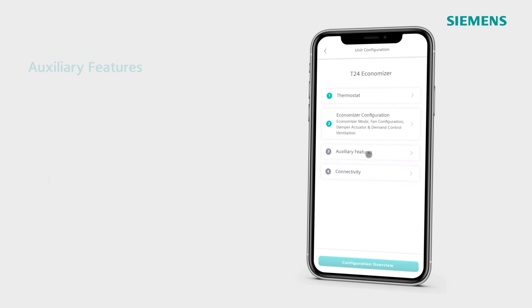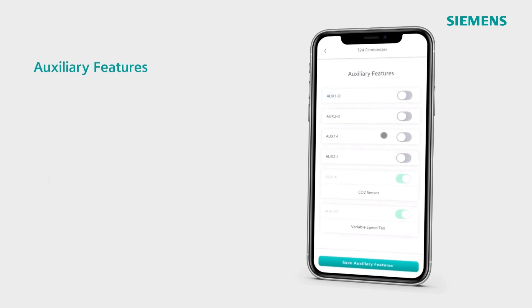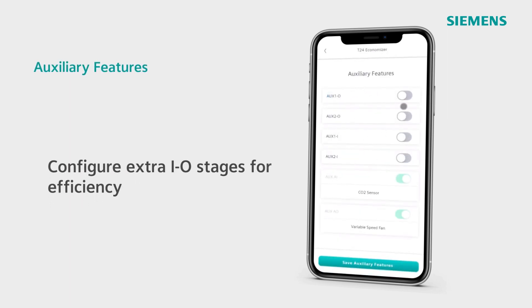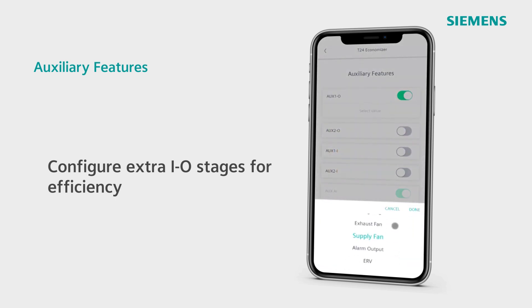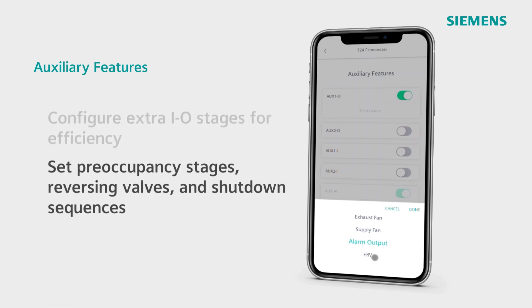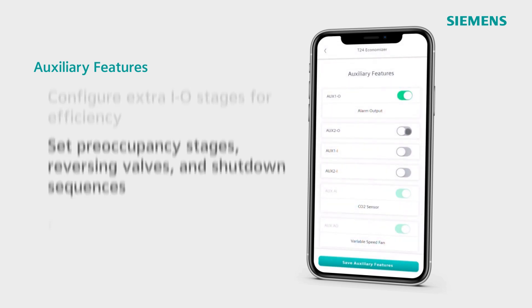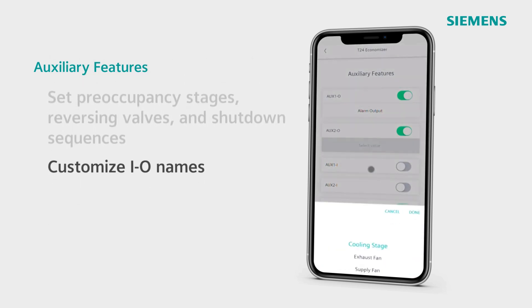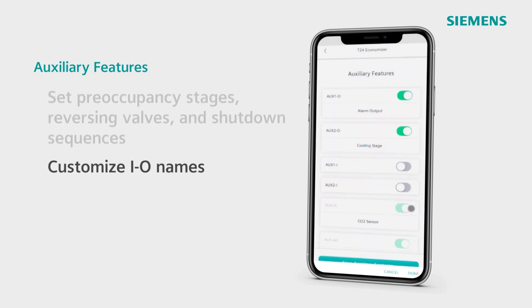Next, let's look at auxiliary features. Climatix Eco has additional input/output, allowing you to choose extra stages of cooling, exhaust fan, supply fan, alarm output, or an energy recovery. You can also set pre-occupancy stages, reversing valves, and shutdown sequences. The input/output names will be updated in the configuration according to the options that you choose.